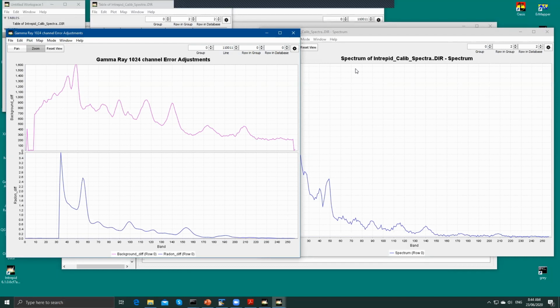If you do QC, whatever the contractor is doing, whichever method they apply, they should show you the calibration spectrum, and you have to have a look at it. All right, that's basically the point. Okay, thank you.